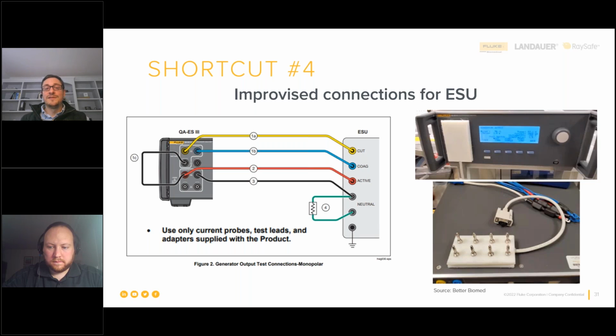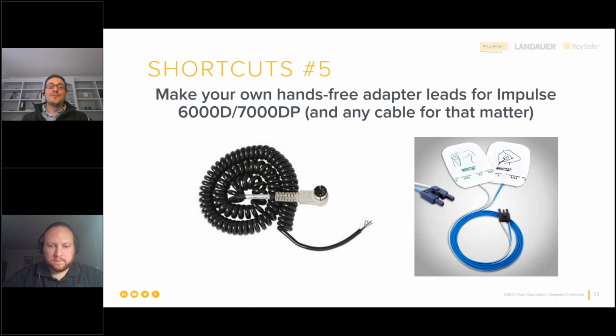And I say that a little bit with an asterisk as we jump on to the fifth shortcut, which is improvisations you can make and should make when Fluke Biomedical doesn't provide the cable that you're looking for. If we have the cable, please use it. It's designed for it. But our industry isn't standardized on connections. In those cases, we make an unterminated cable, right? So it has the Fluke Biomedical end for whatever simulator or analyzer you're using. It has open wires on the other end, and all you're going to do is put a connector on the end. So the cable is safe for its use case, right? It connects to the Fluke Biomedical device properly.